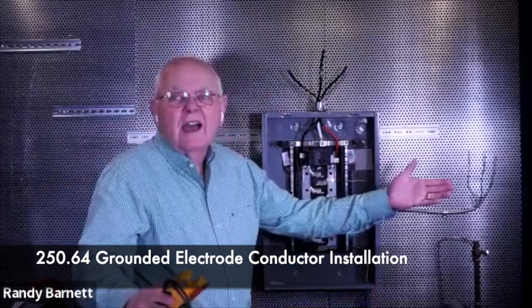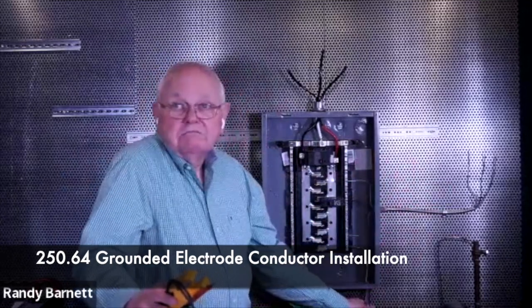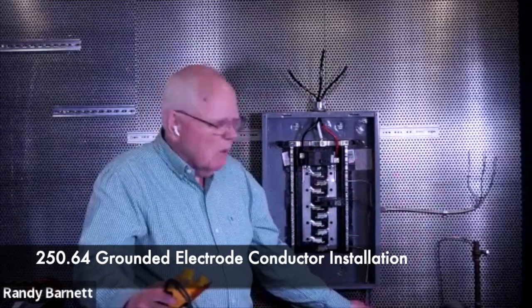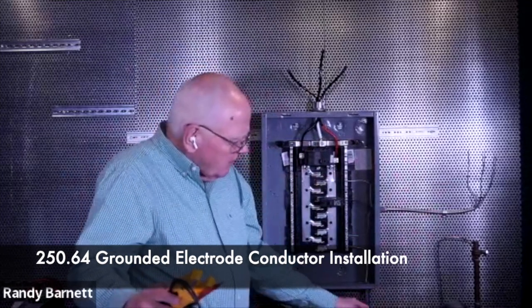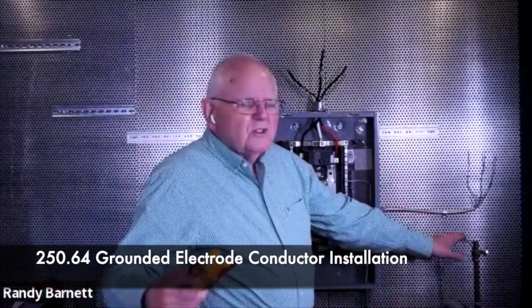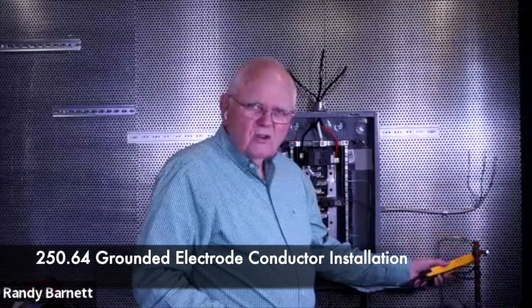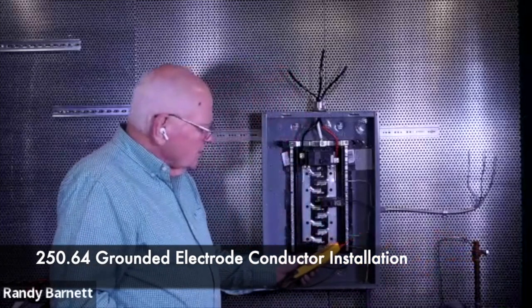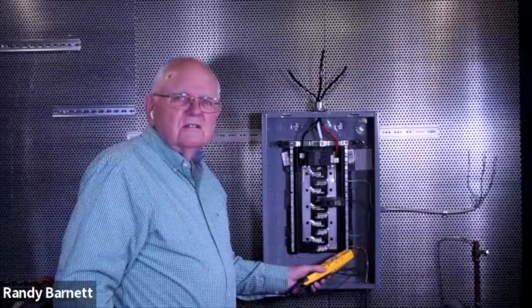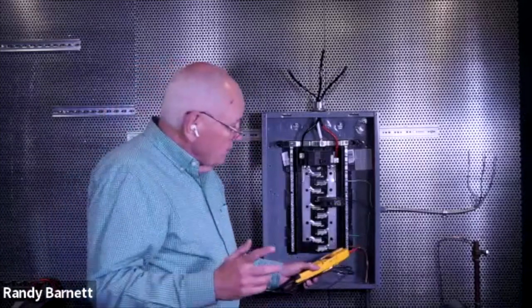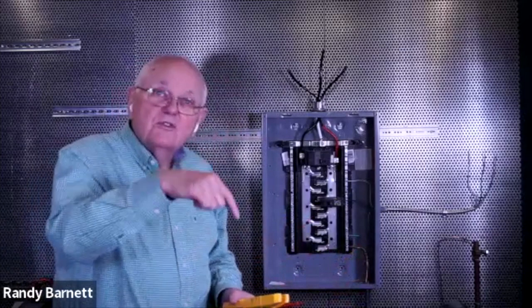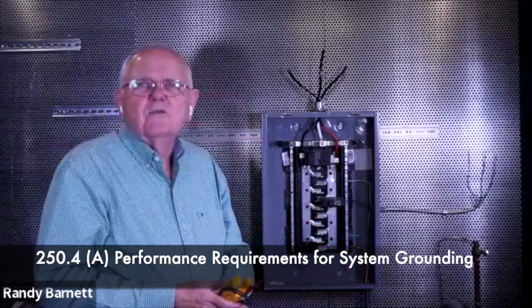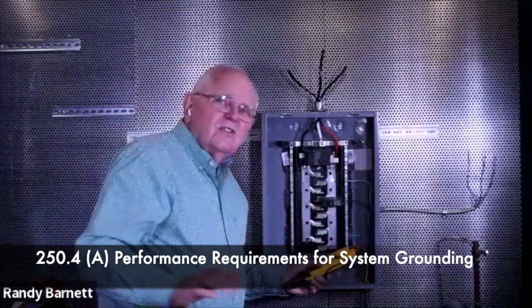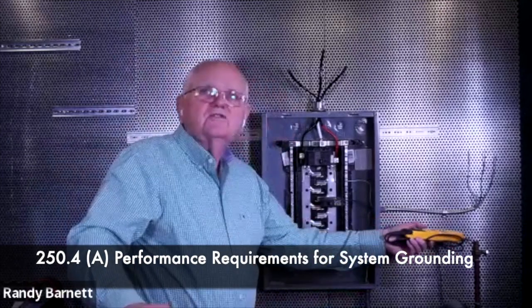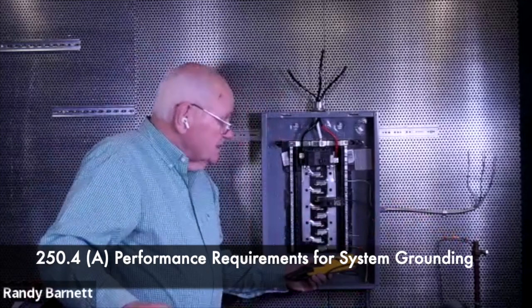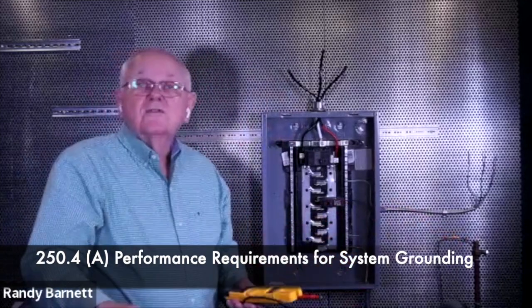We can run it along the side of a house, but quite often we'll use Schedule 80 PVC, won't we, to give it physical protection. Anyway, I'm coming off a little piece of EMT down here, and it goes over here to my grounding electrode. So this conductor is called the grounding electrode conductor. And what's its purpose? Well, we can look back in 250.4 in grounding and bonding, and we find out there are two reasons that I connect the grounding electrode conductor to a grounding electrode. The first reason is to stabilize the voltage to earth during normal operation.